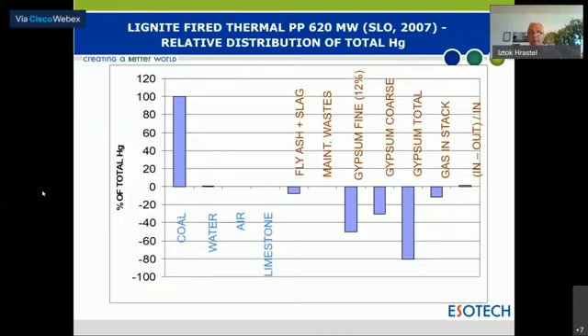In a 620 megawatt thermal plant we observed a very unusual situation: elemental mercury was removed in a classical wet FGD by roughly 76%. Oxidized and particle-bound mercury behaved as expected, with a high degree of removal. The table shows the concentrations of the three species before and after wet FGD.